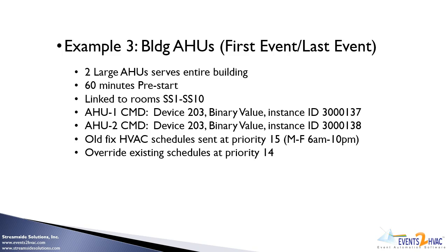The old HVAC schedules were on a fixed HVAC schedule based on worst case building occupancy, Monday through Friday, 6 a.m. to 10 p.m. These schedules were sent at priority 15 command. We will override this and send our commands at priority 14.